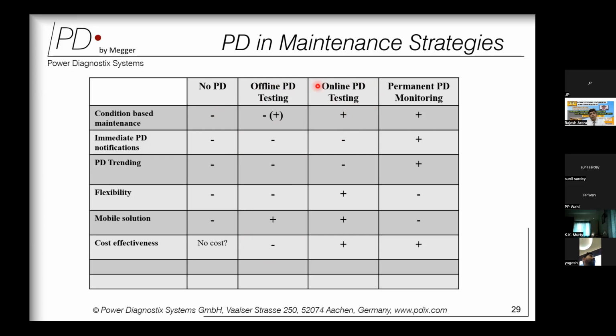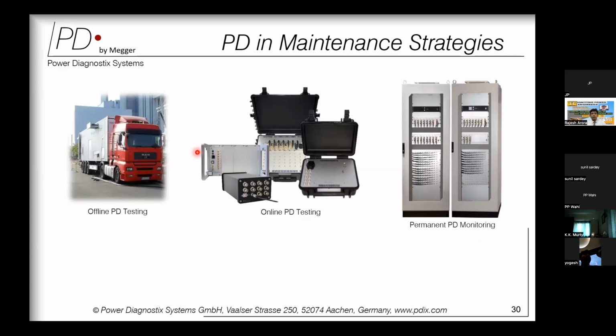You do online PD testing using a portable instrument, but it has some plus and minus. You do permanent PD monitoring, meaning a 24/7 monitoring system can be installed onto the GIS, which again has some plus or minus. That means PD measurement could be available in three forms: offline PD with high voltage applied externally, online PD with a portable instrument, and permanent. But with a portable instrument, you are limited by the individual manual operator's skills to analyze and understand PD, but it offers you the flexibility that you can take it to multiple assets and do a PD measurement.